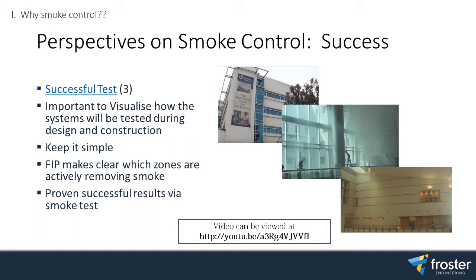The smoke curtains on the lifts shut. It's a makeup air path. Showing fire stopping. We'll show you examples of how that's done incorrectly. Exhaust damper opening to extract. Alright, so that was a successful smoke test. It's important to visualize how the systems are going to be tested, just like you saw when you're designing, and when you're working with the mechanical engineer and the architect, so that you're sure that you covered all bases.